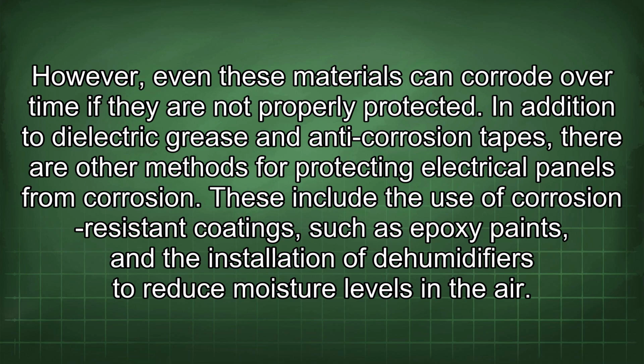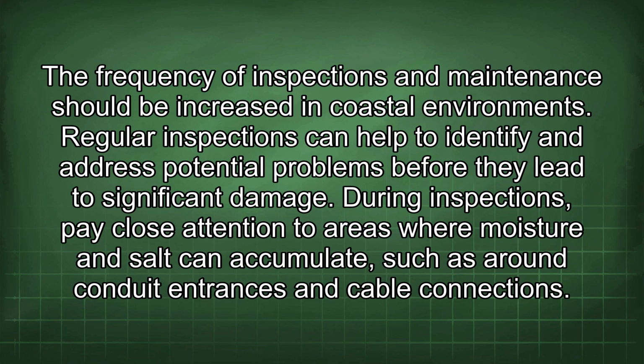In addition to dielectric grease and anti-corrosion tapes, there are other methods for protecting the electrical panels from corrosion. These include the use of corrosion-resistant coatings, such as epoxy paint, and the installation of dehumidifiers to reduce moisture levels in the air. The frequency of inspections and maintenance should be increased in coastal environments. Regular inspections can help to identify and address potential problems before they lead to significant damage.